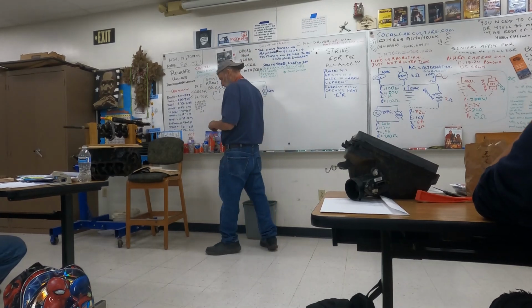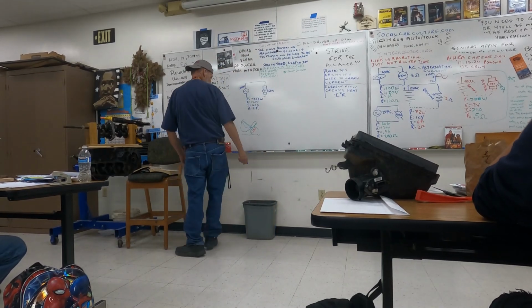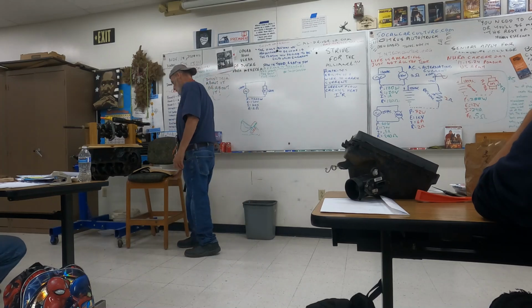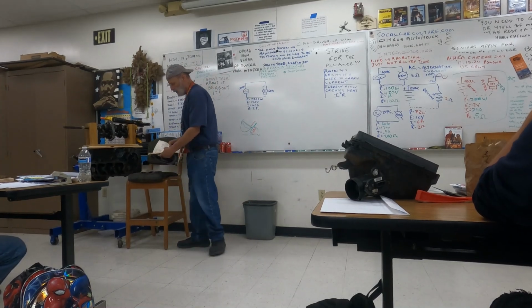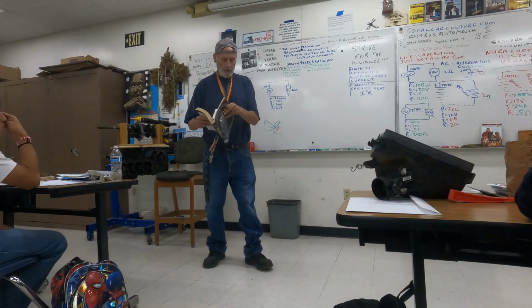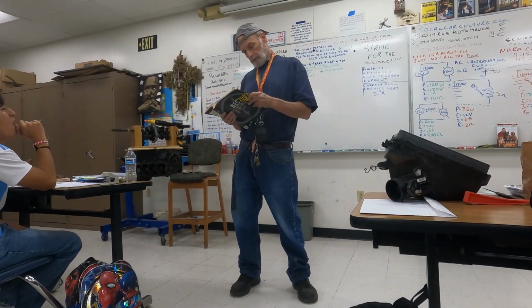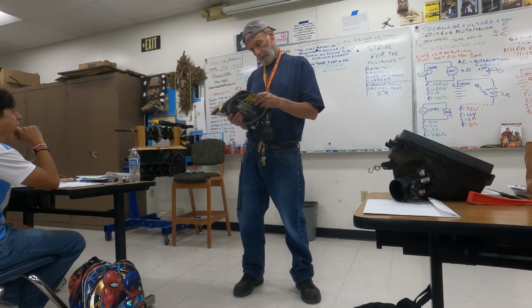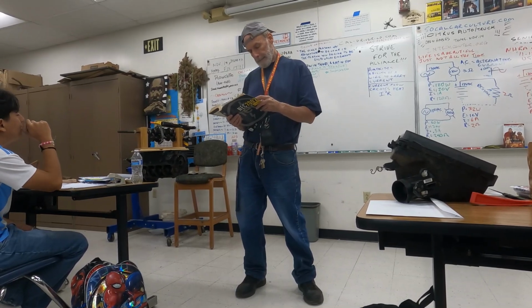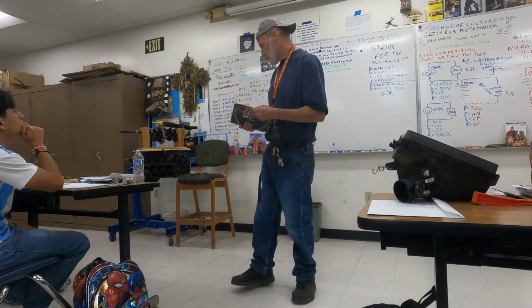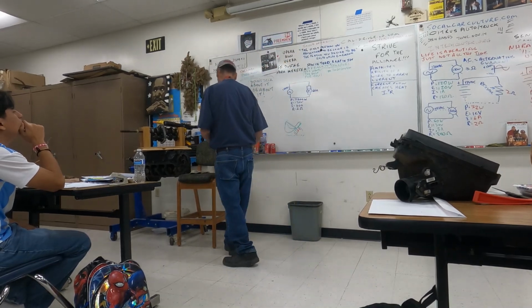So I bring out the National Electrical Code, which is the rules for electrical installations in the United States, and it says that in order to carry 60 amps, I need to have a number 6 wire. That's a problem, because number 6 wire is pretty freaking big.